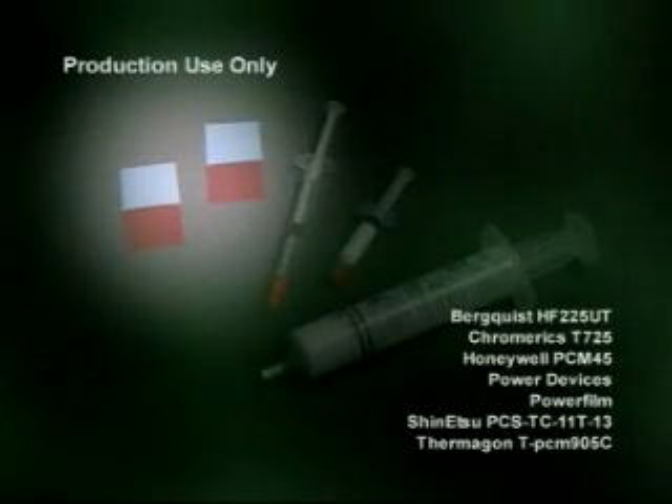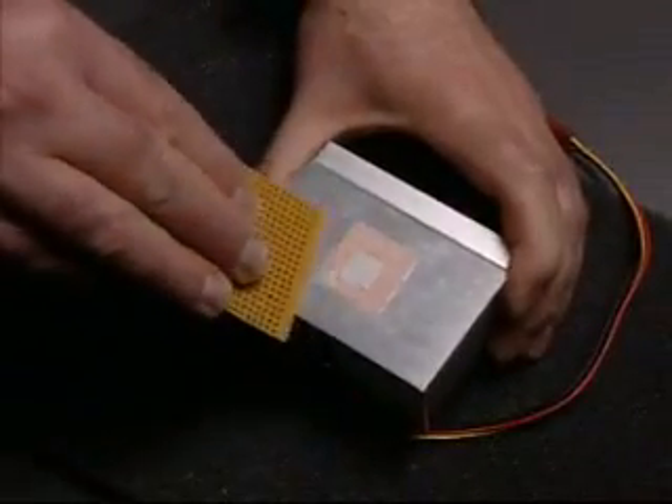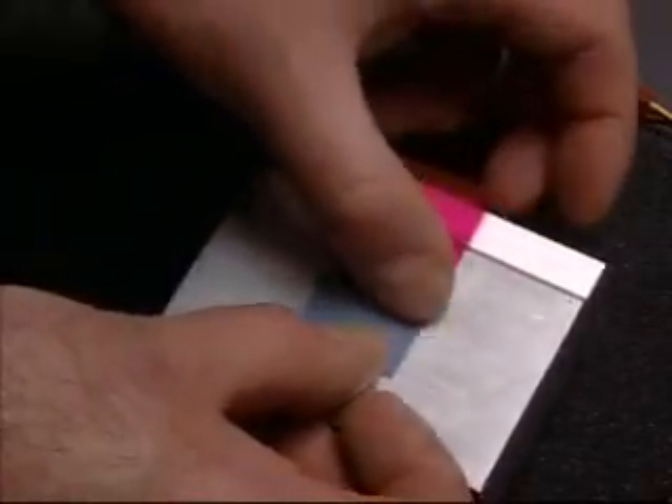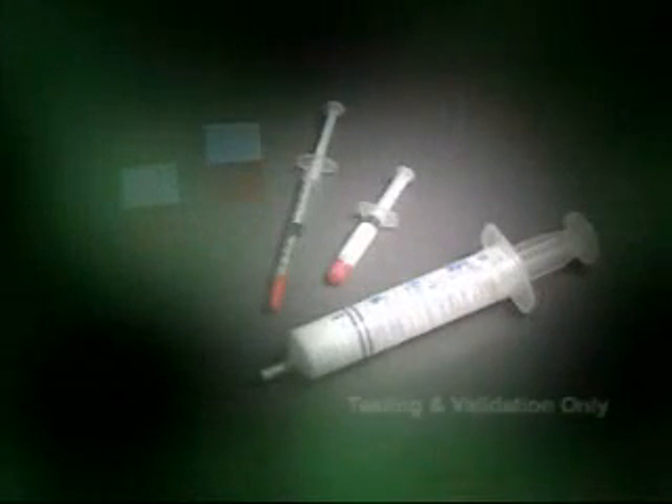Use a thermal pad for long-term production installations. Never reuse a thermal pad — always clean the heat sink and processor and replace the pad appropriately. Thermal grease is only recommended for development, test, and validation purposes, not in a production environment.